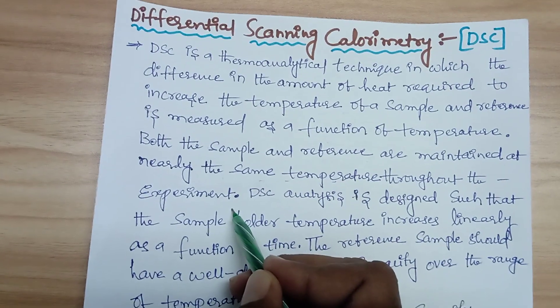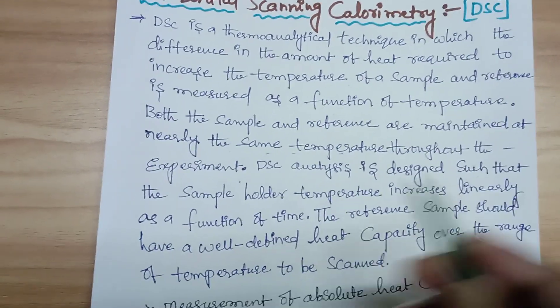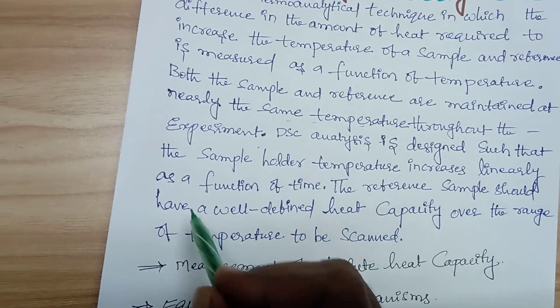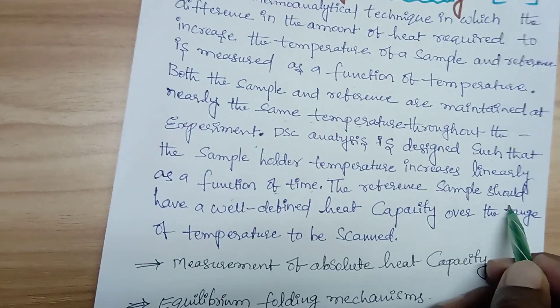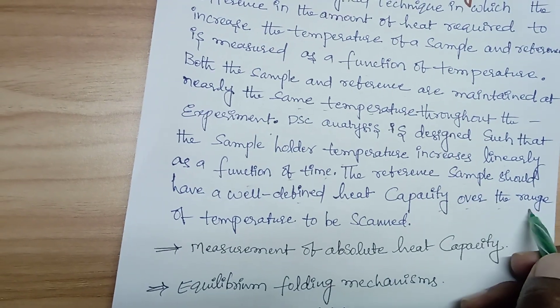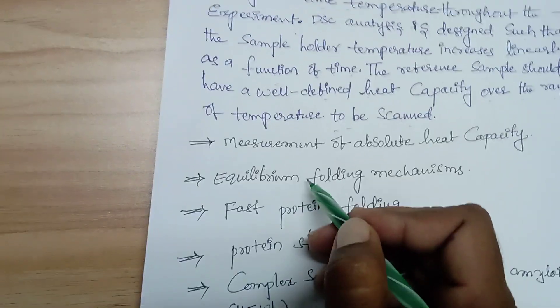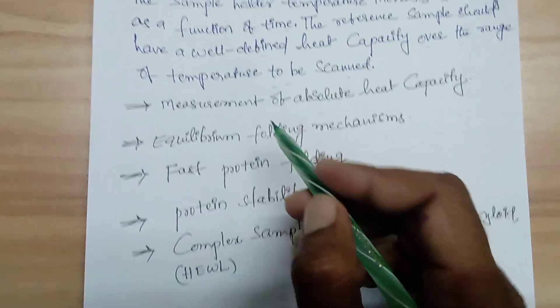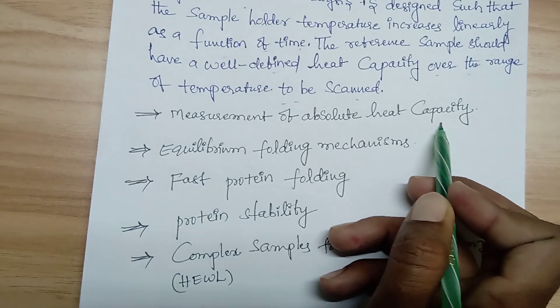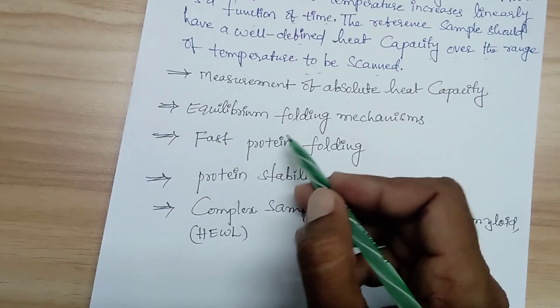A special feature of DSC is that the analysis is designed such that the sample holder temperature increases linearly as a function of time. The reference sample should have a well-defined heat capacity over the range of temperatures to be scanned. One key application is the measurement of absolute heat capacity — for example, measuring the absolute heat capacity of a protein using DSC.